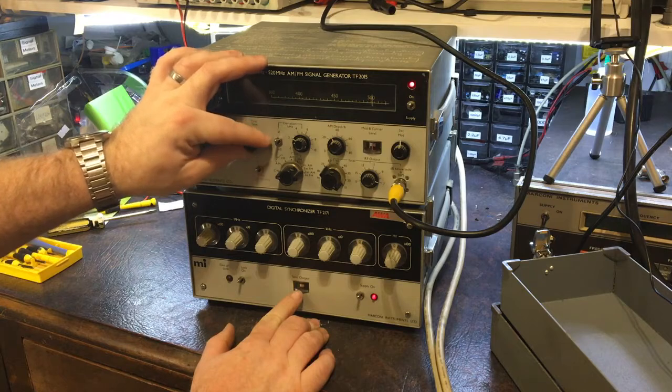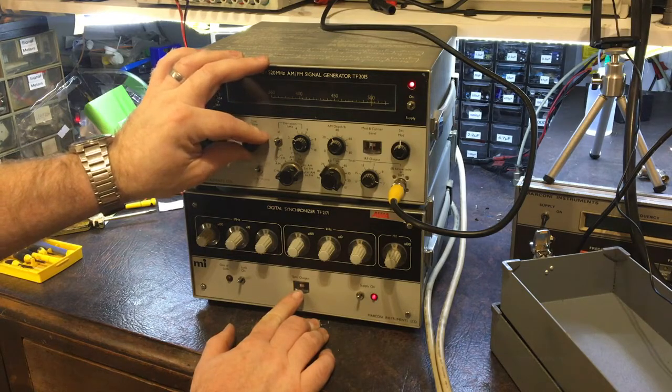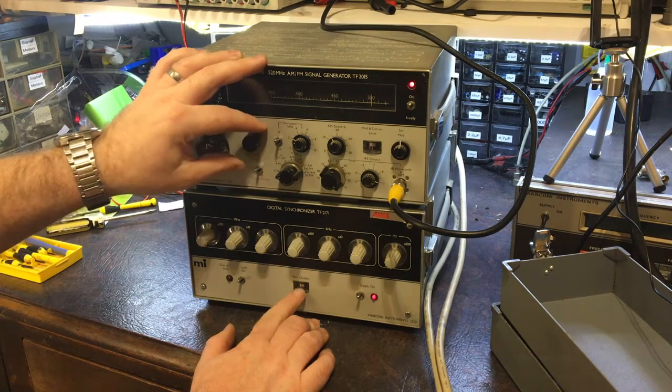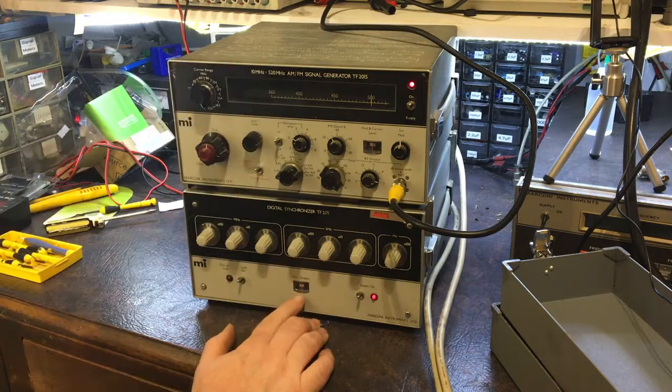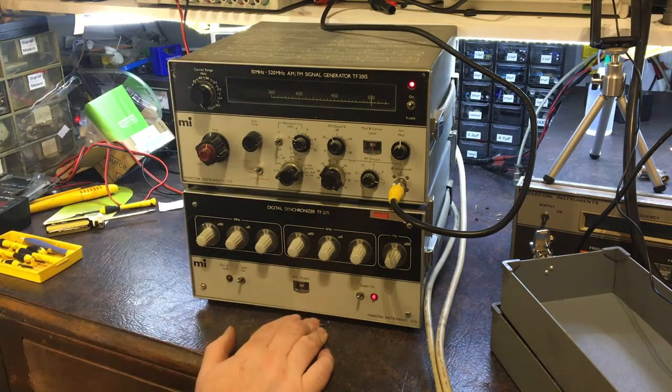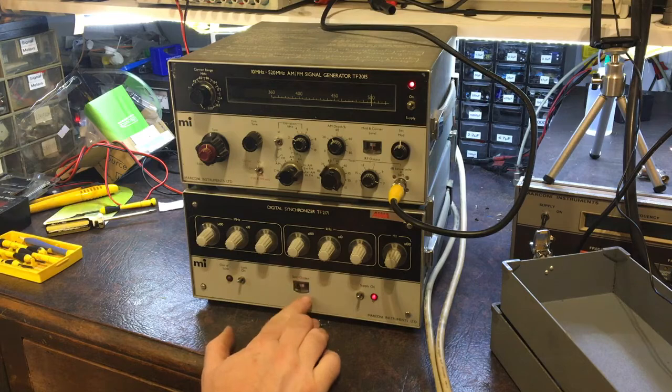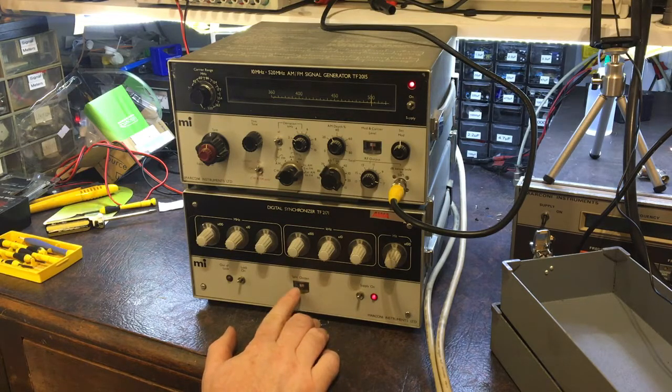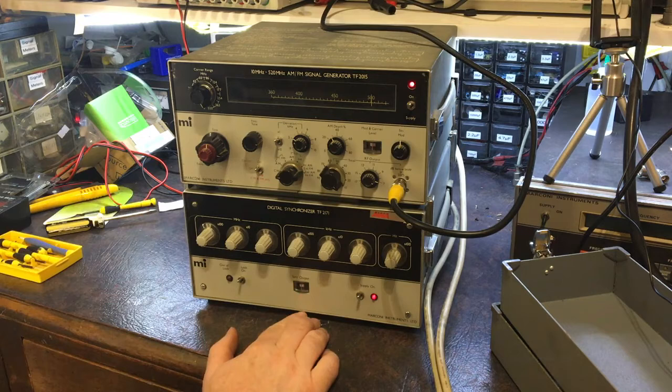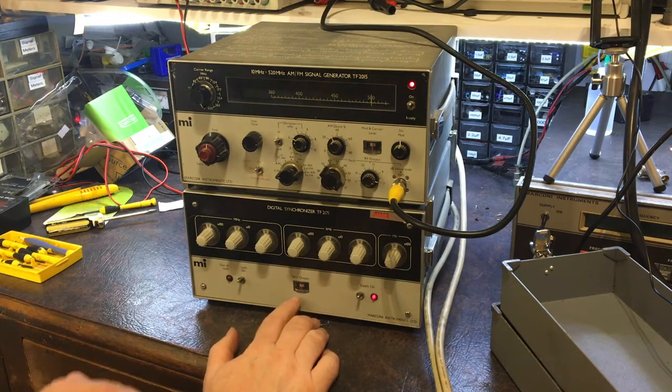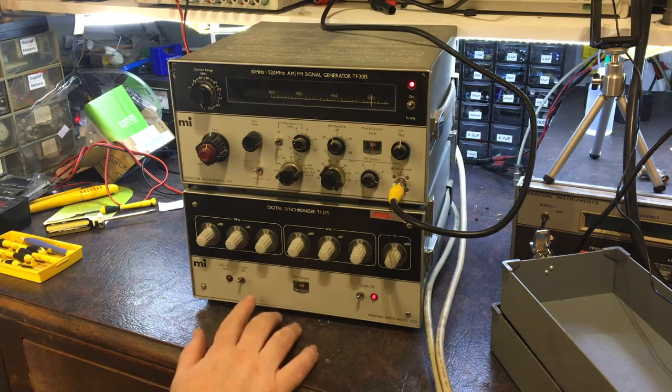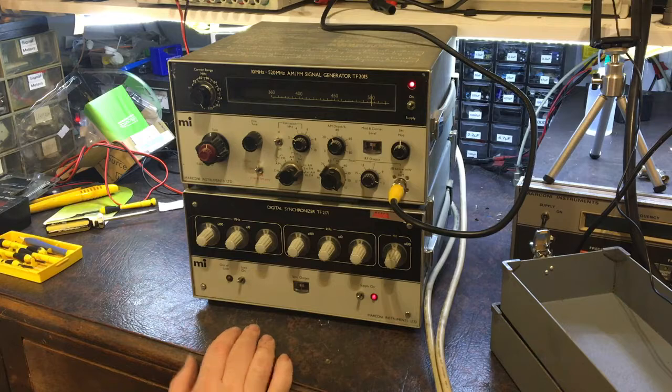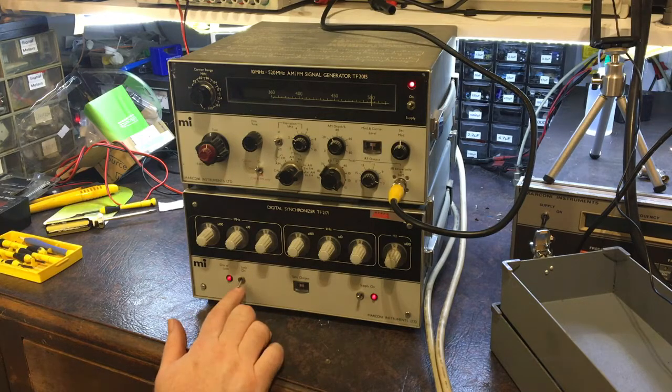And if you look on the synchronizer, you can see a level just down here. Hopefully you can see that needle. And you're supposed to tune it until it's in the middle of the meter, so it lines up. That gives you proper control. That's basically a relative voltage output. So it tells you what the output voltage is relative to the frequency.